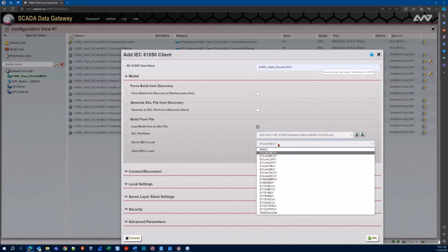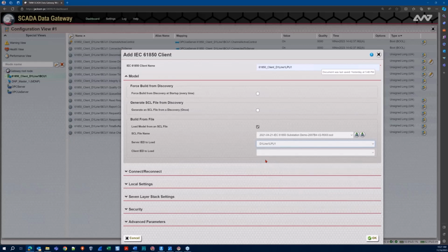The next step is selecting which of the multiple IEDs defined in this particular SCD file I want to create a client for. If this was a CID there might be only one, but because this is an SCD, it describes a whole substation and the many devices in it. So I'll just select the D1 line 1 LPU 1.